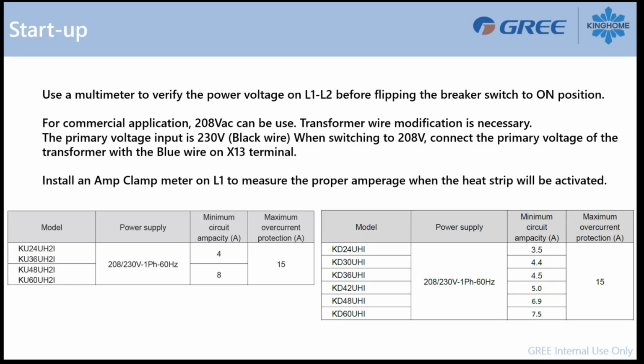Basically, the transformer is using 3 wires. You can select if you want to use the black wire. The black wire is installed as a default for 230 volts. But if you have 208, it is important to switch the black wire to the blue wire on the terminal X13. That will help the transformer to work with the proper voltage and give you a real 24 volt output.